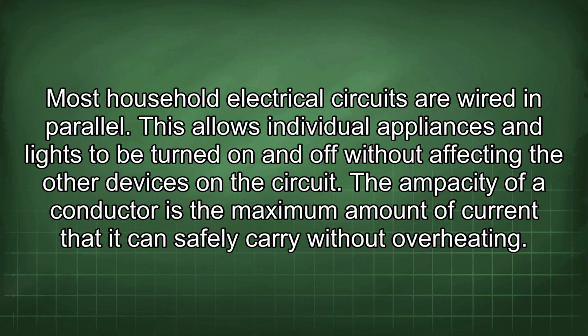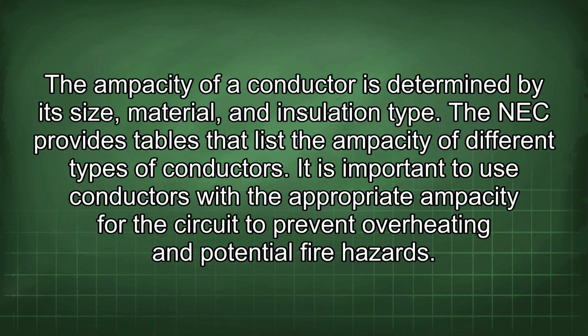The ampacity of a conductor is the maximum amount of current that it can safely carry without overheating. The ampacity of a conductor is determined by its size, material, and insulation type. The NEC provides tables that list the ampacity of different types of conductors. It is important to use conductors with the appropriate ampacity for the circuit to prevent overheating and potential fire hazards.